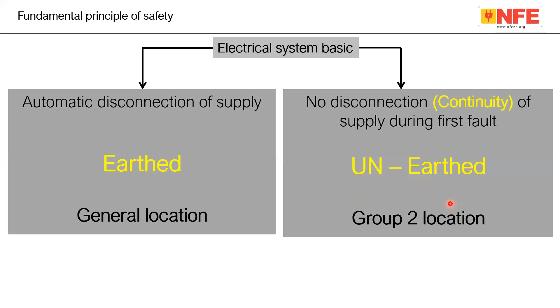Similarly, for Group 2 locations, an unearthed system is used because continuity of supply is necessary. What is missing in almost all our electrical installations is a measure called protective equipotential bonding, as shown in the picture. For example, sub-panel, motor body, metallic parts, metal pipes — all these must be interconnected to a common bus bar.